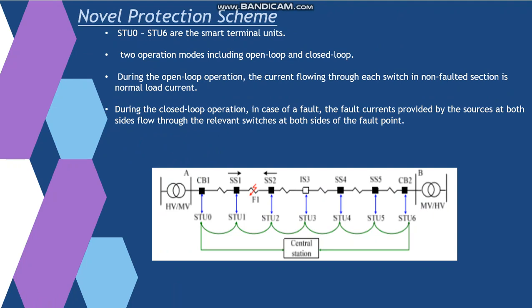On the screen you can see the distributed protection scheme for the distribution system. During the open-loop operation, the current flowing through each switch in non-faulted section is normal load current. During the closed-loop operation, in case of a fault, the fault currents provided by the sources at both sides will flow through the relevant switches at both sides of the fault point.